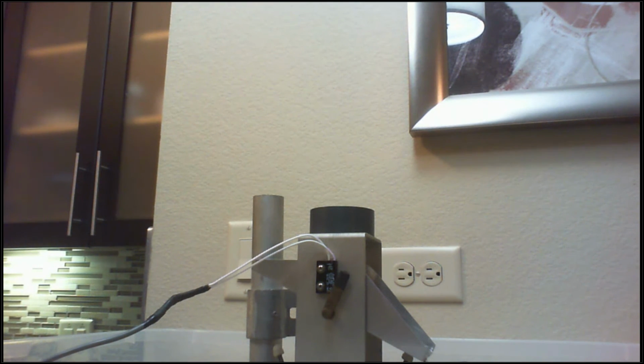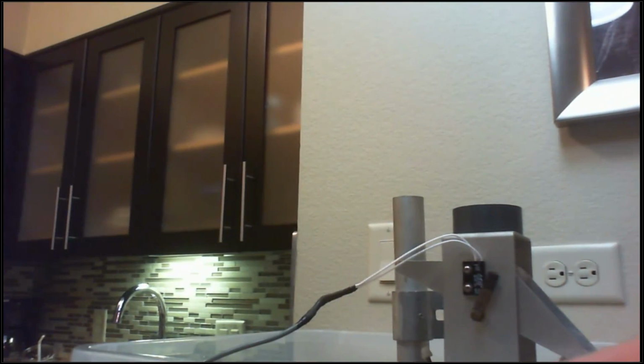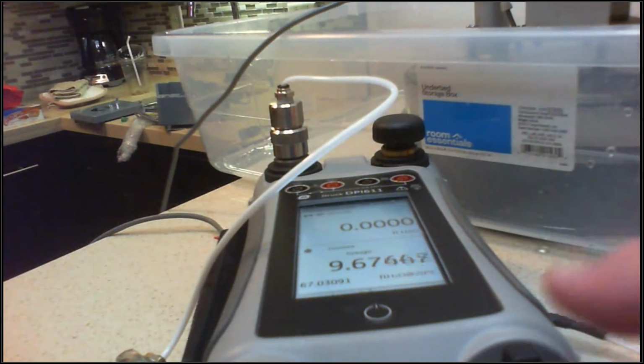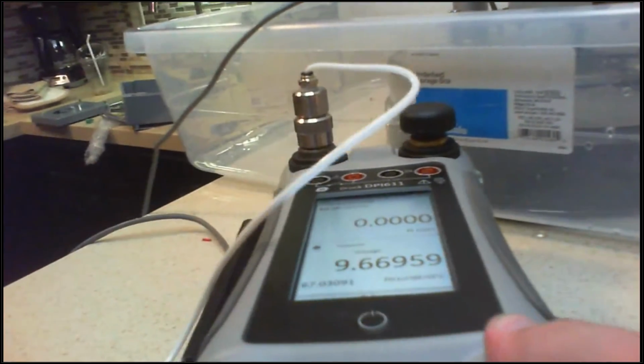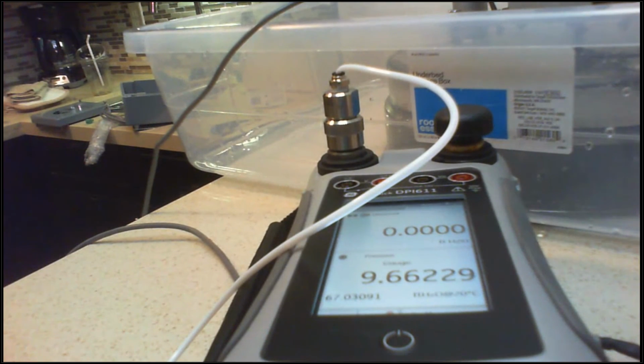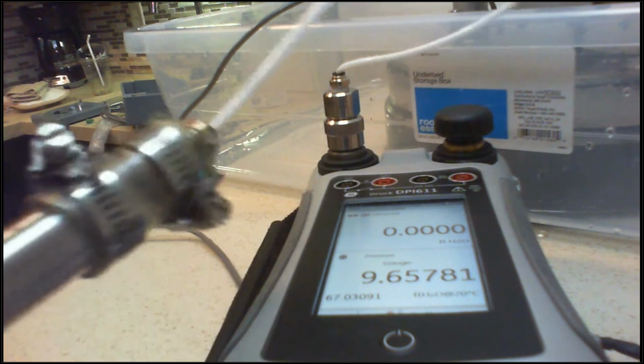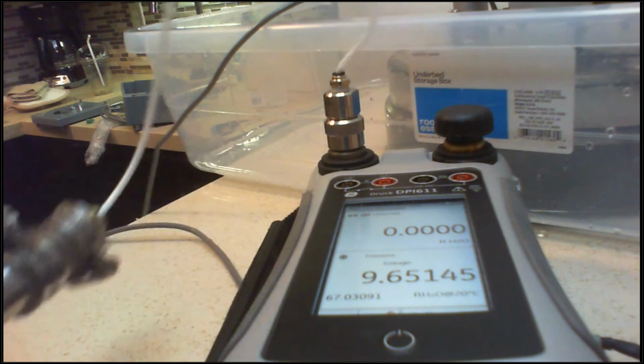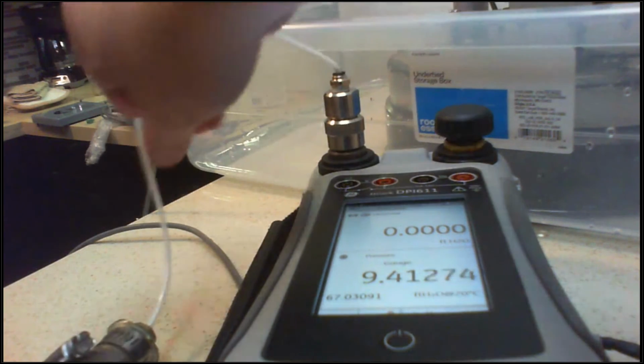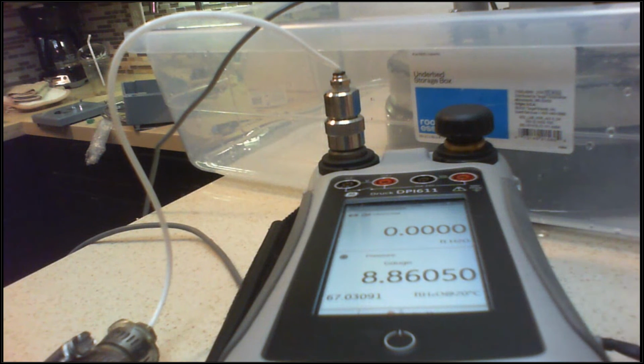So the calibrator we're going to be using today is a Druck DPI611. That's the specification sheet that I showed you guys earlier. And I'm going to try to adjust the camera so that you can see it. See how well this works. I know it's not going to be easy to see because I need to pump it from basically the bottom of it. But I've got the calibrator set up with PT right here hooked up to it. And right now you can see I've got 8.83, 8.81. It's dropping a little bit, feet of water on it.